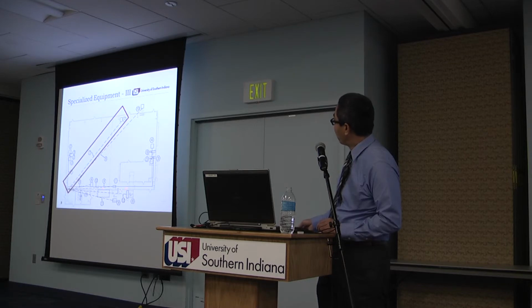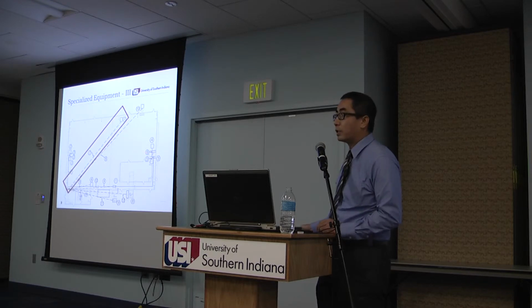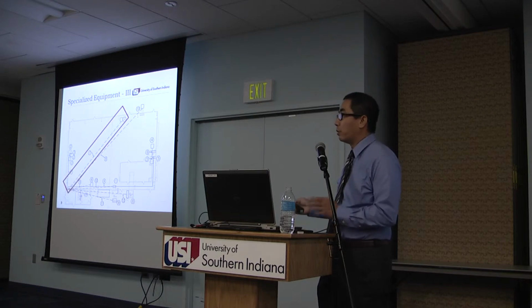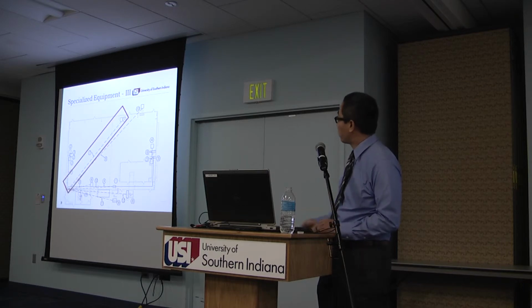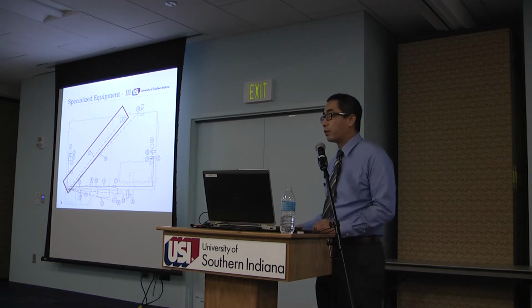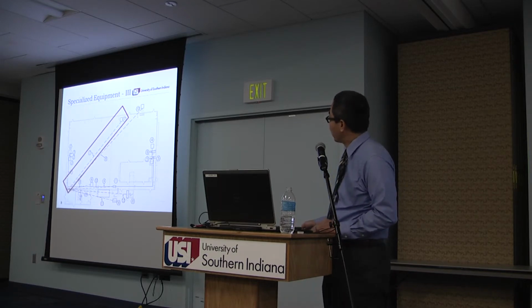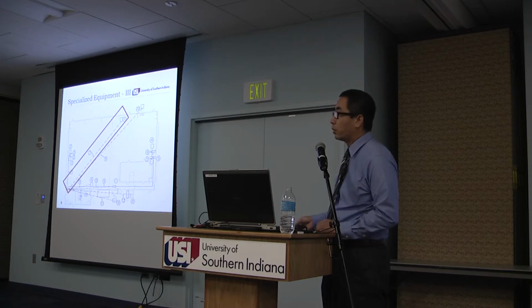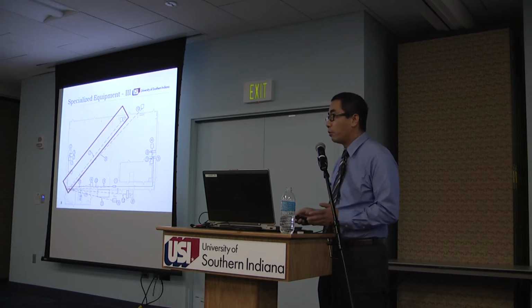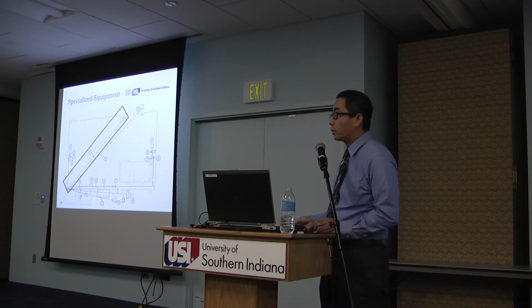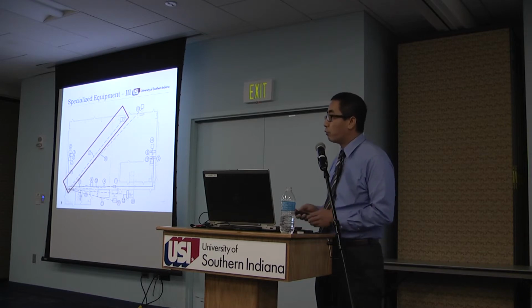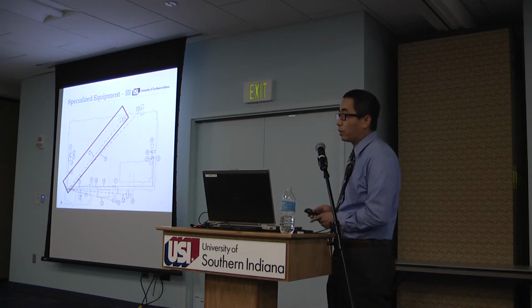And this is how we run the wire for the other equipment. You see the solid line that mainly serves the roll-up door. That's the metal tubing we run above the ground, just around the perimeter of the building. And this dashed line indicates the PVC pipe will be buried underground. The reason we run it this way is because we can reduce the length of the run. If you have too long a run, you have a large voltage drop, just for the wire itself. If you have too much voltage drop, you can damage the equipment itself.